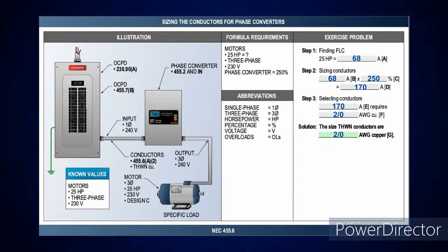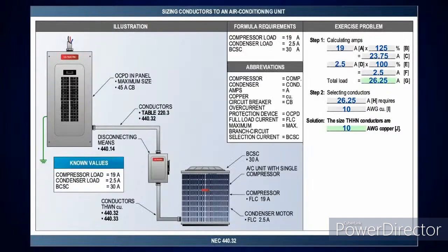And if you look at a 25 horsepower motor, in this case, I've got a 3-phase, 230 volts. So I'll go to table 430.250, come down, pick up your 230 volt, come across, pick up 25 horsepower. It'll tell you it's good for 68 amps. And then it'll tell you in 455.6A2 to take that at 250%, which is going to give you 170 amps. Then you go look at the next size above that in table 310.16, and that's going to be 175 amps, which is a 2-aught copper conductor. So pretty basic.